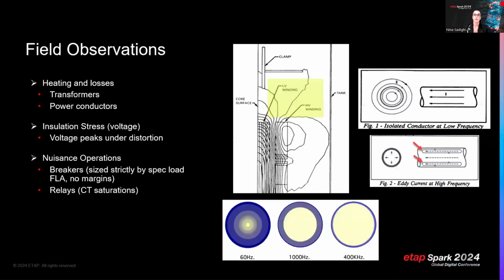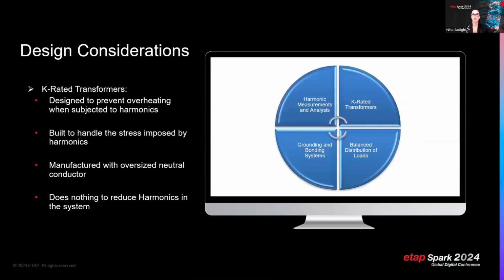So field observation, whenever we have harmonics, it's going to be heat losses on transformers and conductors, which then leads into energy losses. Then there's going to be stress on the insulation of equipment, which then reduces the life cycle and the lifespan of the equipment. And then there's definitely always nuisance tripping with relays, saturation of CTs that then cause equipment to misoperate, breakers and fuses as well. So design considerations, of course, grounding and bonding is very important, and ensuring that we perform harmonic analysis early on in design so we can mitigate the design considerations we need and incorporate them in there.